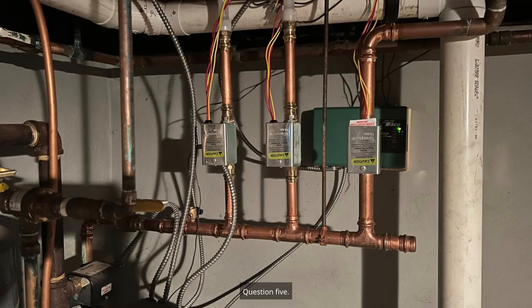Question 5: Would zone upgrades fix what you actually hate? Most 'I need a new boiler' complaints are really comfort complaints — cold rooms, uneven heat, pipes that bang. A new manifold with proper zone valves, new thermostats, and a controller can often deliver the comfort improvement people are chasing for under $3,000, leaving the boiler in place. That's what I did at the Mohawk cottage, and the heat finally felt right.